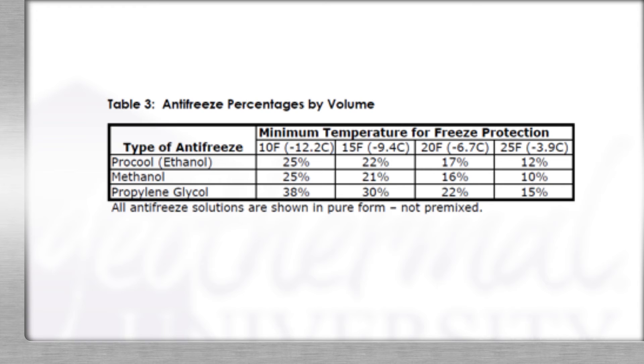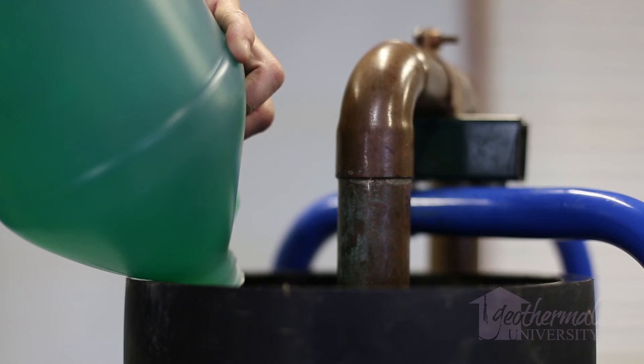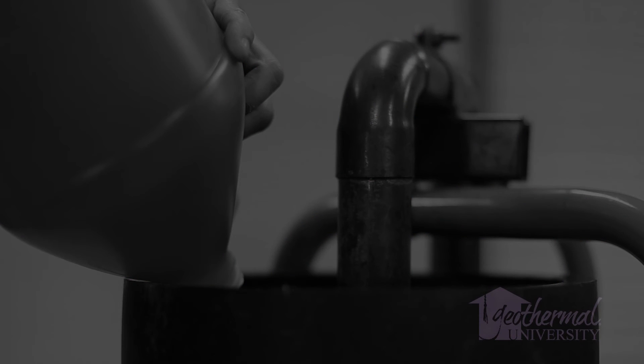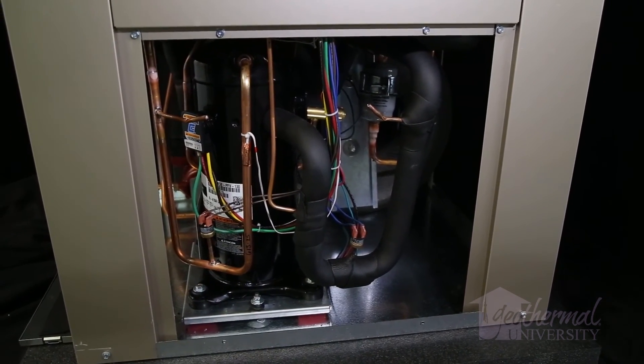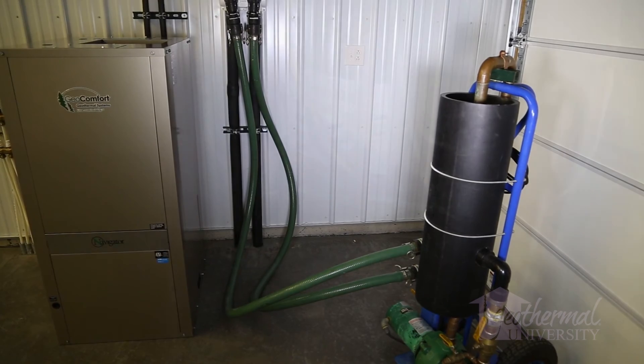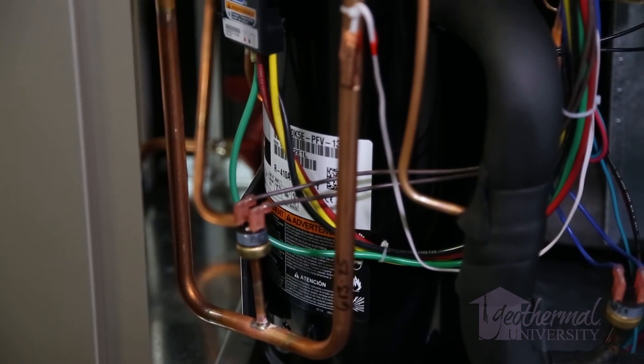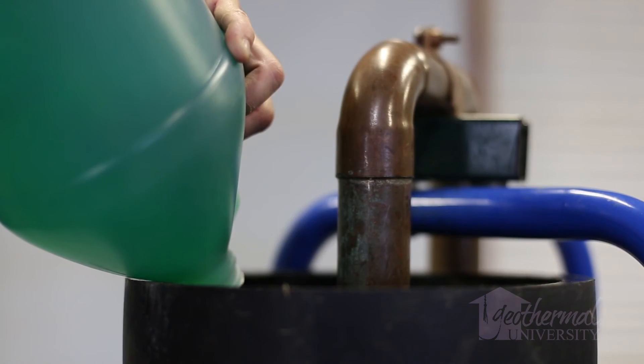Some parts of the country do not use antifreeze. In areas where minimum entering loop temperatures drop below 40 degrees or where piping will be routed through areas subject to freezing, antifreeze is required.